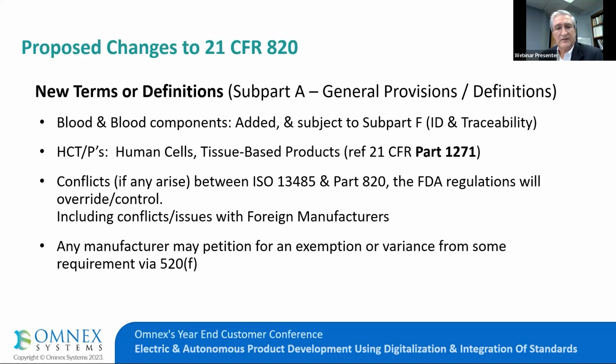Another interesting thing here is that any manufacturer may petition for an exemption on some requirement by using this form 520F. I think that's also currently used in 21 CFR Part 820, so that will continue.